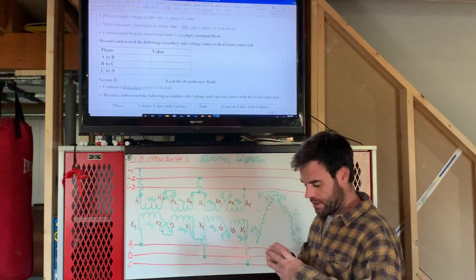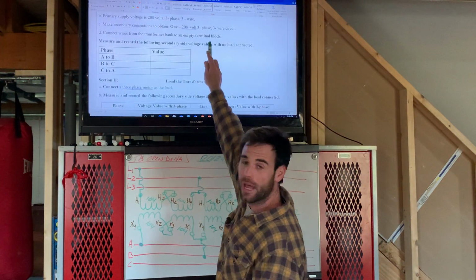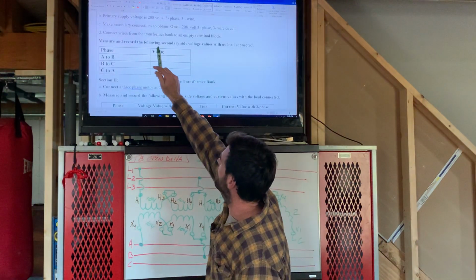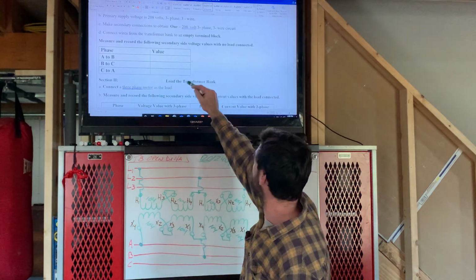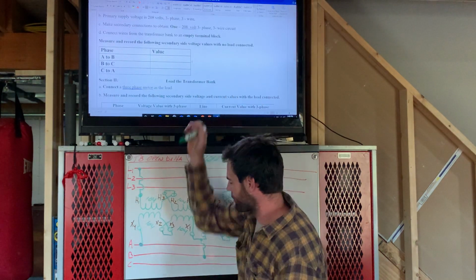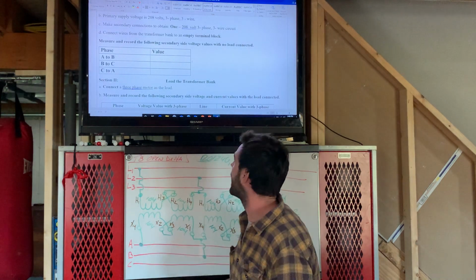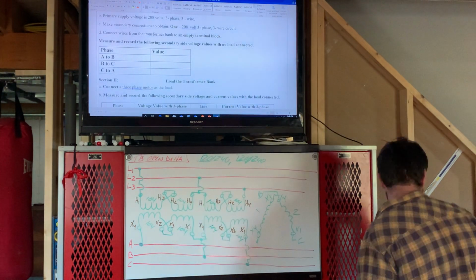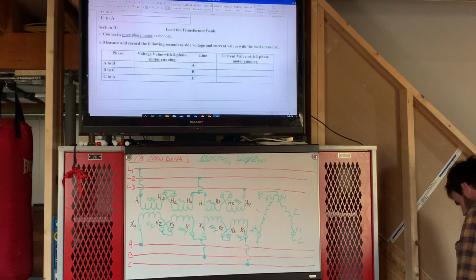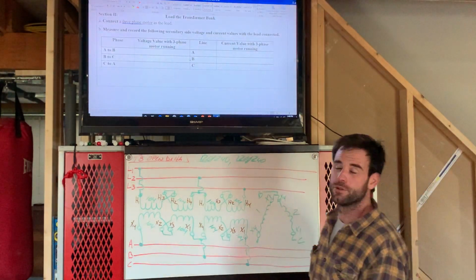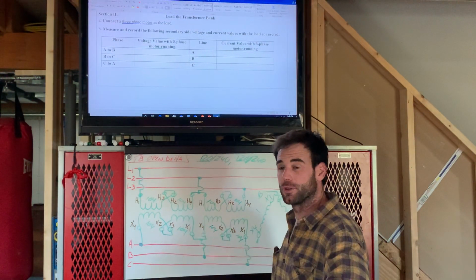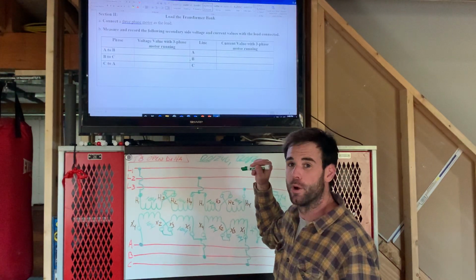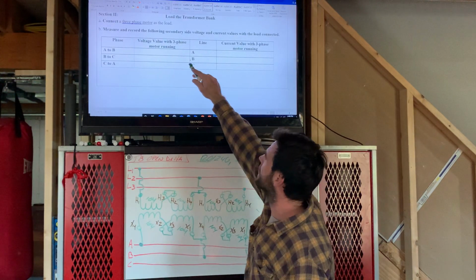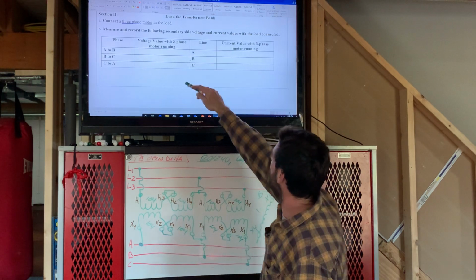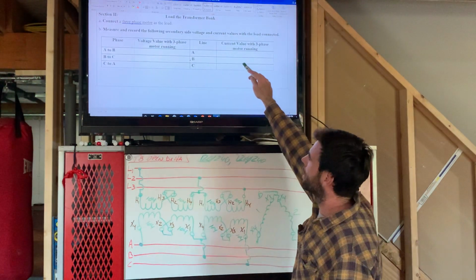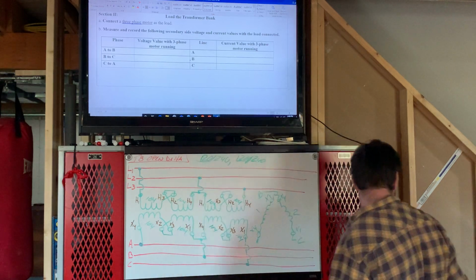After you do that, we want you to hook this up to an empty terminal bank, and then we're going to measure and record the following secondary voltages with no load connected. So you're going to measure A to B, B to C, C to A, and write those values down. After you do that, come off of that blank terminal strip and go to the 3-phase motor in your booth. Connect to that and then take 3-phase voltage readings with the motor running and then current readings with the motor running. These are all on the secondary side.